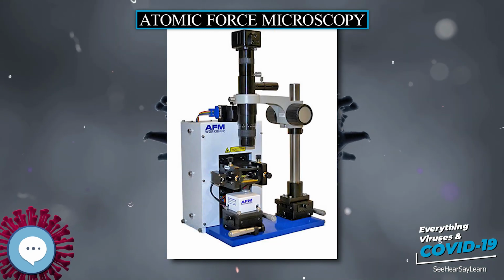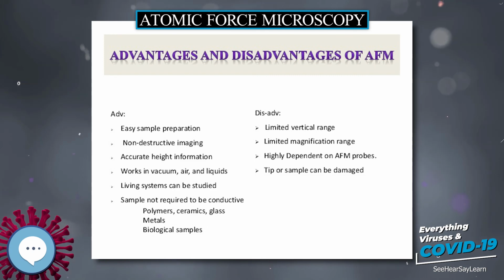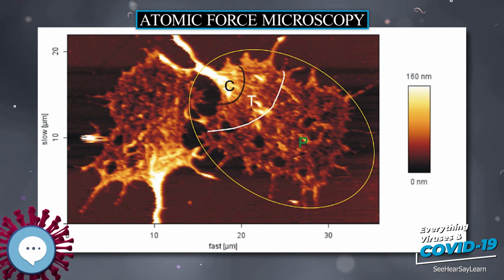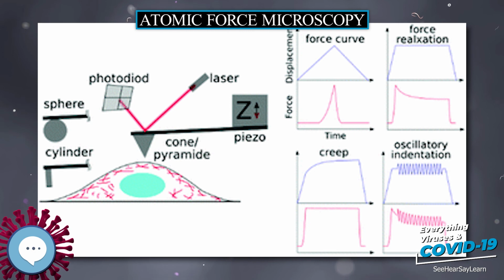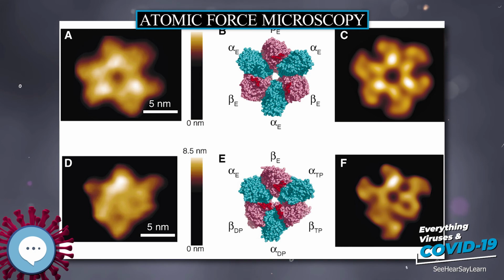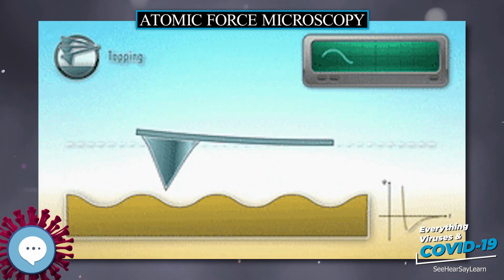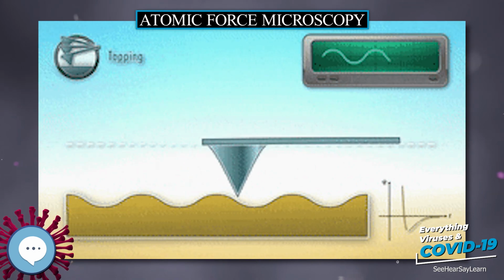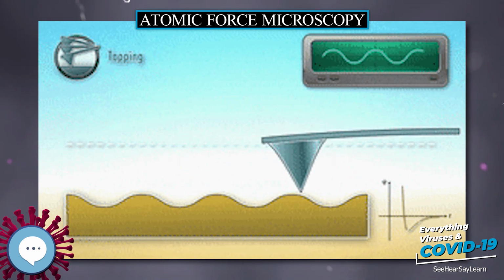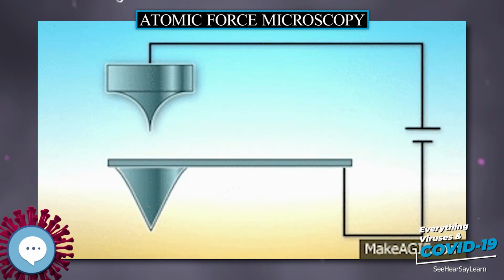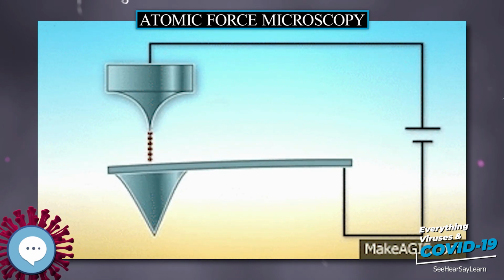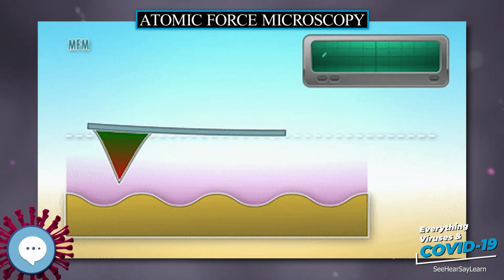In tapping mode, the cantilever is driven to oscillate up and down at or near its resonance frequency. This oscillation is commonly achieved with a small piezo element in the cantilever holder, but other possibilities include an AC magnetic field, with magnetic cantilevers, piezoelectric cantilevers, or periodic heating with a modulated laser beam. The amplitude of this oscillation usually varies from several nm to 200 nm. In tapping mode, the frequency and amplitude of the driving signal are kept constant, leading to a constant amplitude of the cantilever oscillation as long as there is no drift or interaction with the surface.